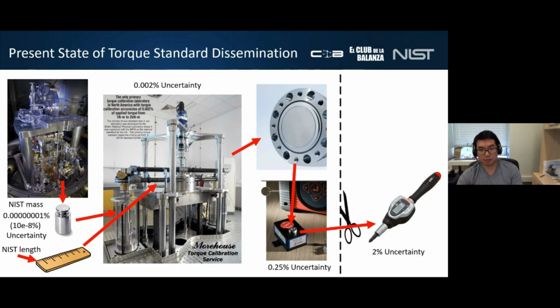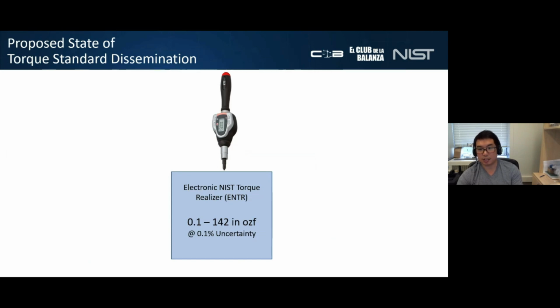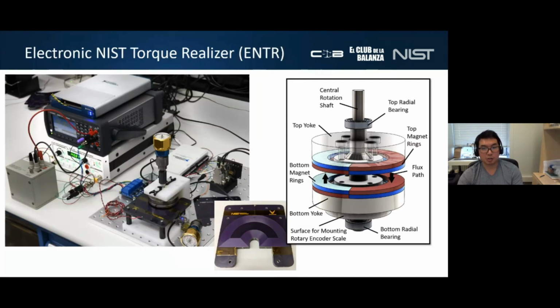So our plan is to create a device that'll take us from this stuff to this, right? Some black box, or in this case, this blue box, that can directly interface with torque tools and give direct SI traceability to 0.1% uncertainty. So enter the ENTR, the electronic NIST torque realizer. What you see in this photo is everything you need to build a primary torque standard traceable to the new quantum SI via electrical standards, just like a Kibble balance.